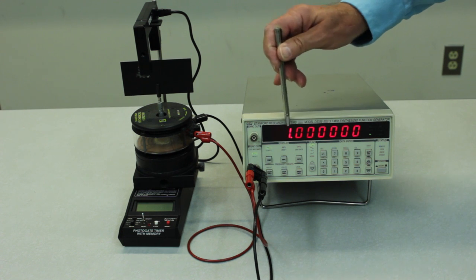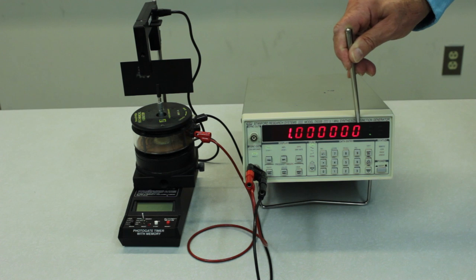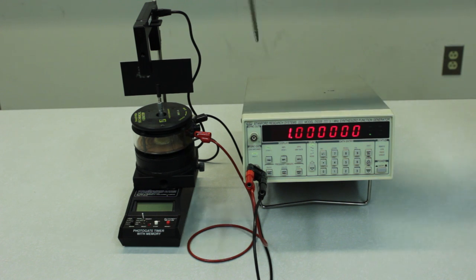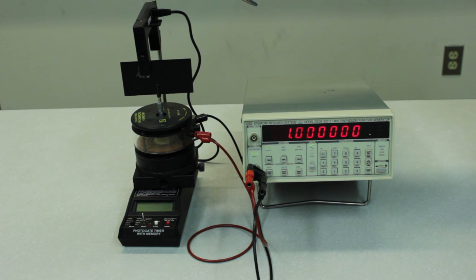So what we've got here is a frequency of one hertz, which is precise and accurate to a microhertz, a part in 10 to the sixth. That's a good calibration standard to use for the timing device, which will give you the time to a part in 10 to the fourth. So we want to calibrate with a known time standard that's much more precise and accurate than the timing device that we're going to use.